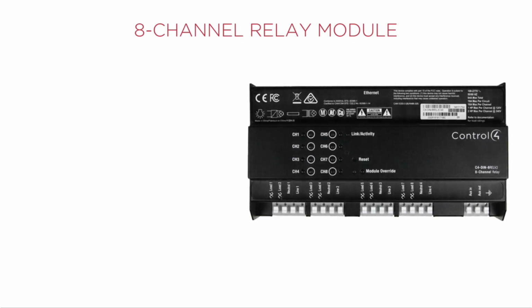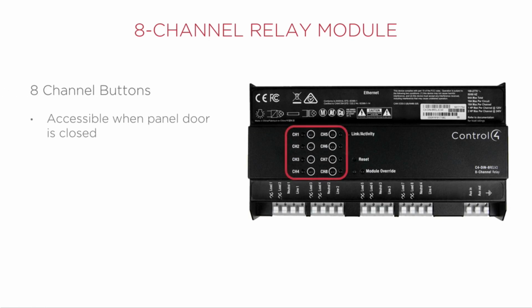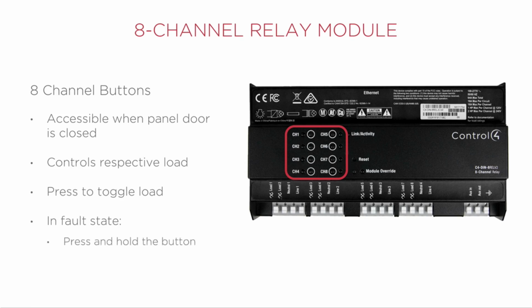Like the dimmer module, the Control4 relay module features 8 channel buttons that are accessible when the panel door is closed and controls each respective load. Pressing the button will toggle the load. In a fault state, the button can be pressed and held to reset any fault.